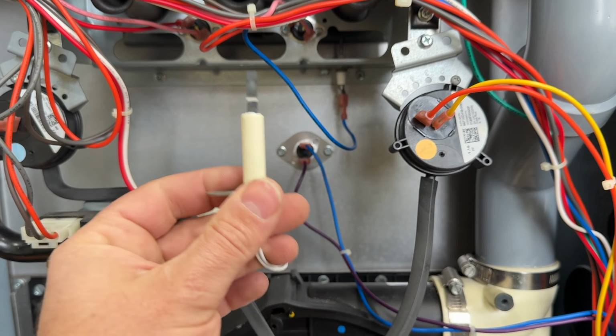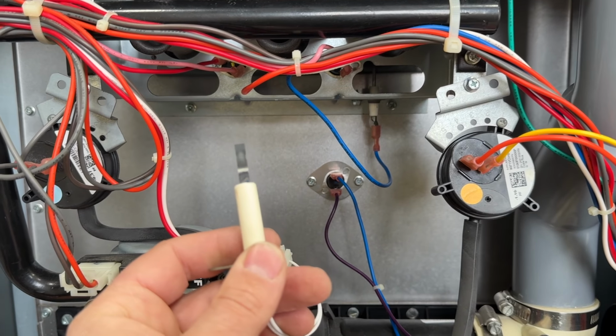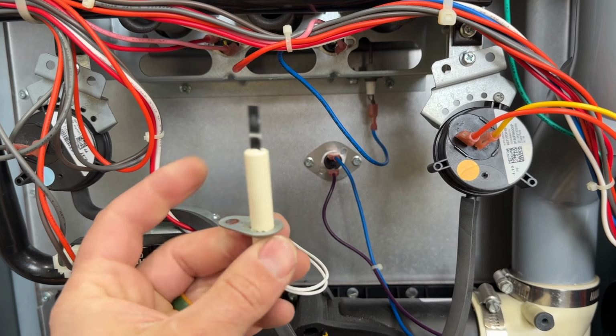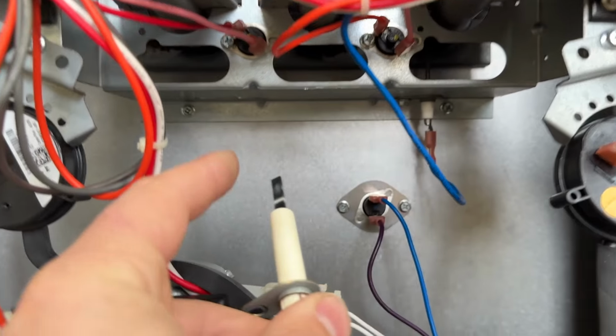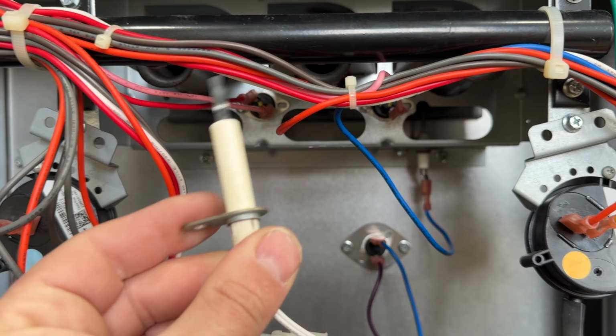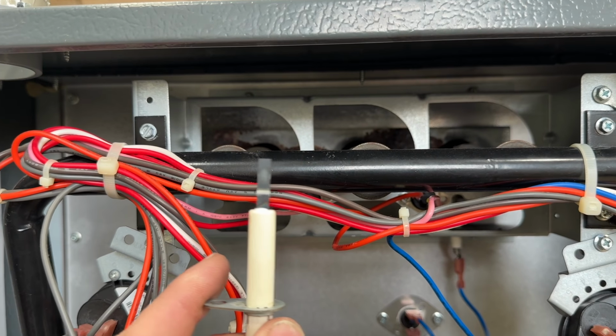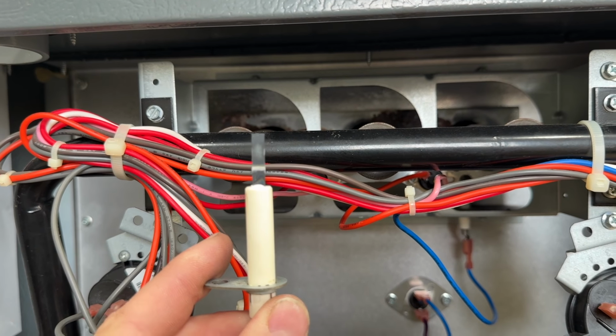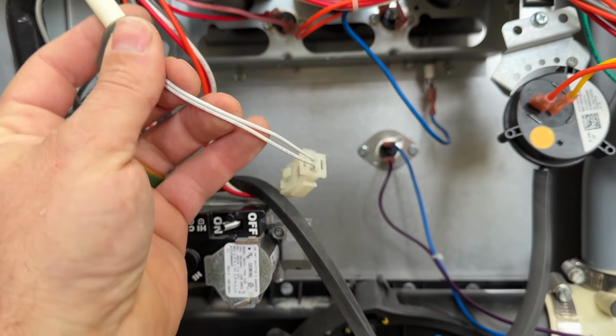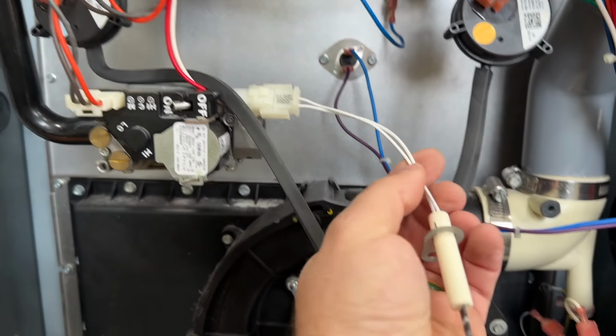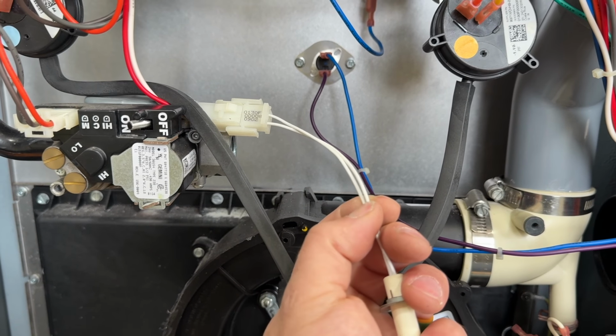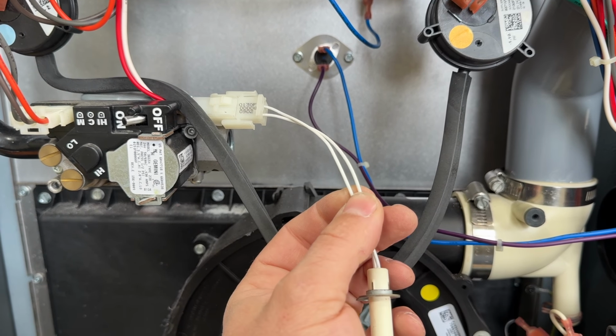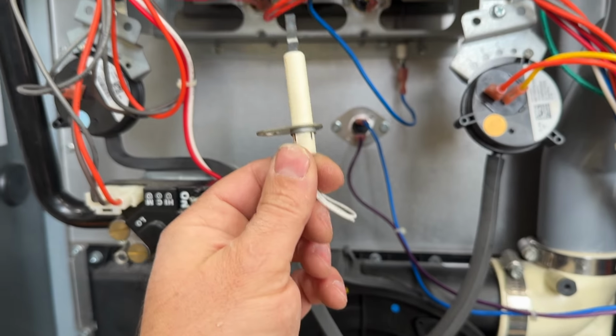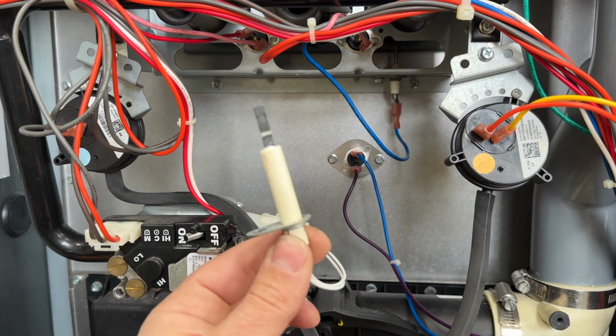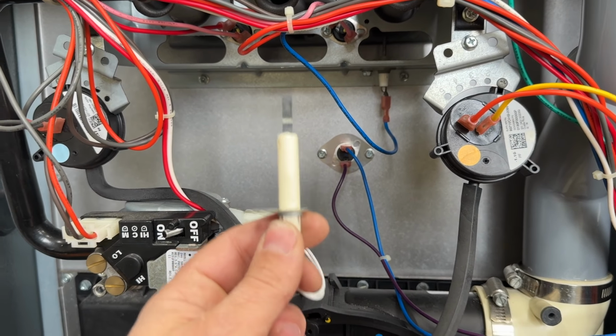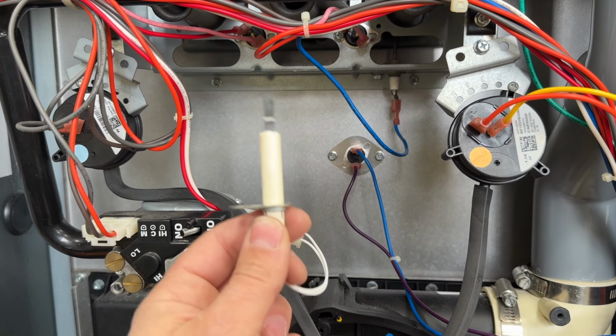And what you can do is actually replace it with one of these. I'll leave a link in the video description of a universal hot surface igniter. All you have to do is make sure you put it in the same hole as the old one and make sure that it's lined up with the side of the burner to where it will ignite, and it's as easy as that. They come with wire nuts, so you can actually cut this right here and just wire nut one wire to each. The polarity doesn't matter, and it's as easy as that. I'm going to do a separate video on how to upgrade your igniter to one of these, as these are far superior to the other ones that are extremely brittle.